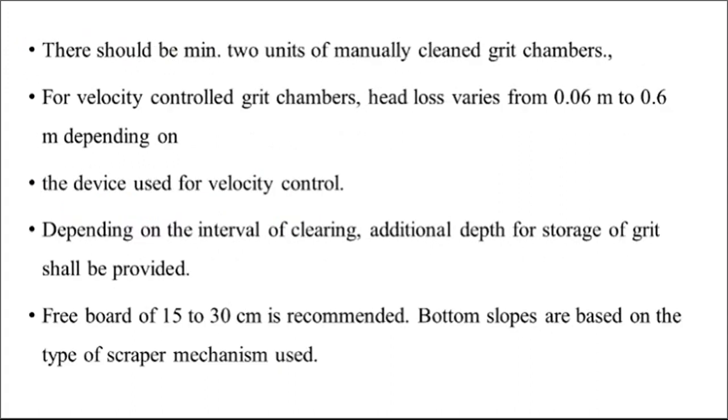Next one, there should be a minimum of 2 units of manually cleaned grit chamber. For velocity controlled grit chamber, head loss varies between 0.06 meter to 0.6 meter depending upon the device used for velocity control.